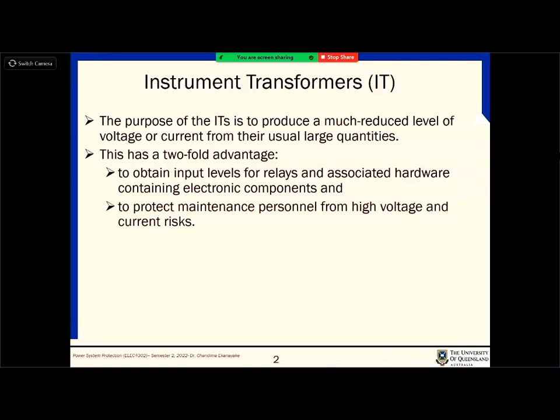The other important thing is that for high voltage assets like transmission lines, power transformers or generators, the maintenance crew usually don't go there and do a lot of things. Then you have to take it out of operation, or you need to have some safety precautions for that work. But at the relay operation level, maintenance crew or engineers have to frequently visit those places and do some measurements. These lower voltage or lower power levels give you personal safety, so that reduces the risk.